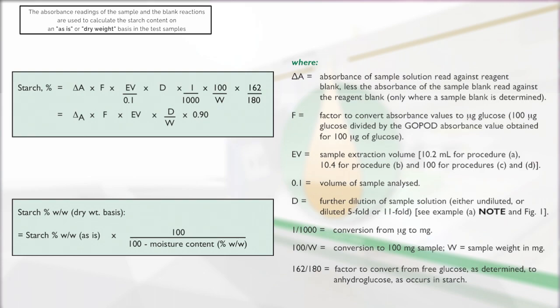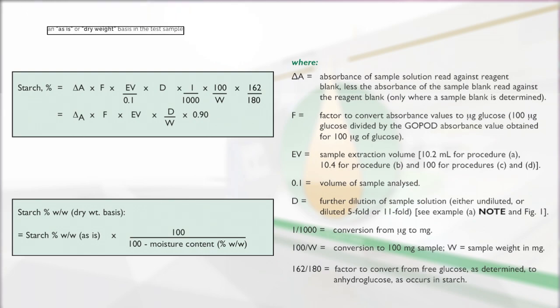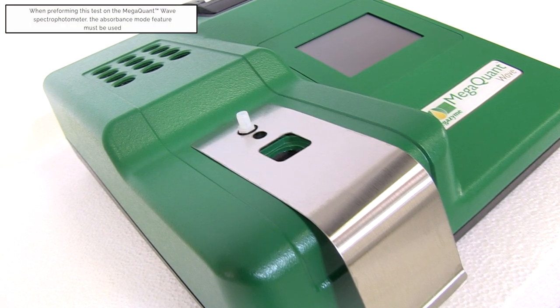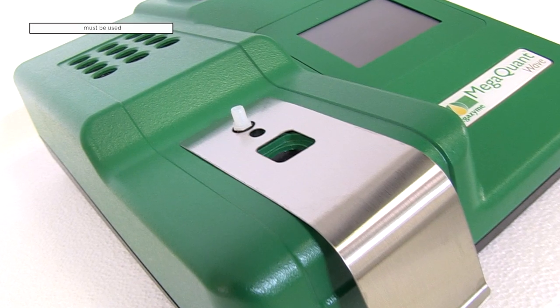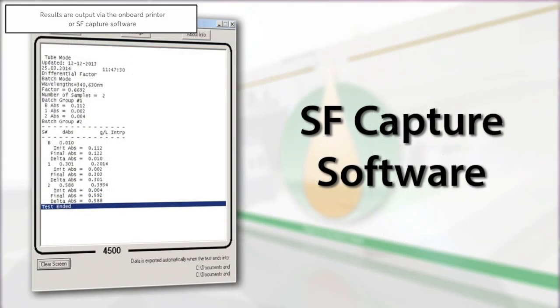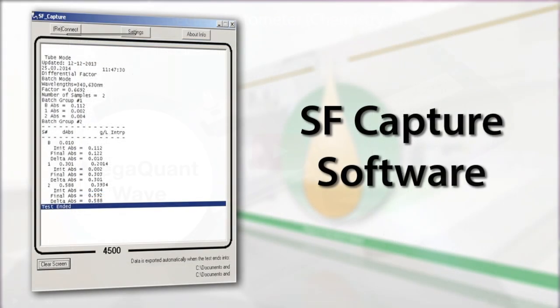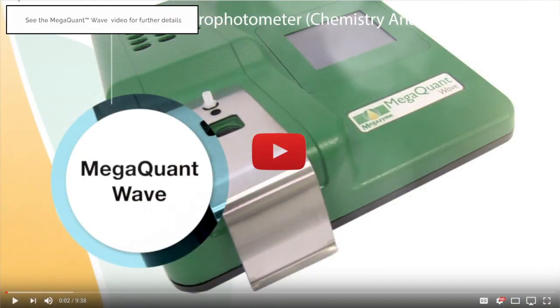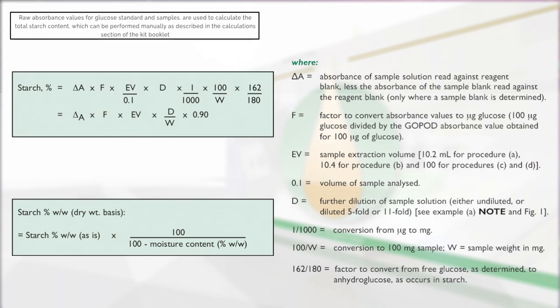The absorbance readings of the sample and the blank reactions are used to calculate the starch content on an as-is or dry weight basis in the test samples. When performing this test on the MegaQuant Wave spectrophotometer, the absorbance mode feature must be used. The results will be printed via the onboard printer or the data can be exported to a computer using the SF Capture software. In absorbance mode, the results output are raw absorbance values for glucose standard and samples. Therefore, the calculations of total starch content can be performed manually as described in the calculations section of the kit booklet.